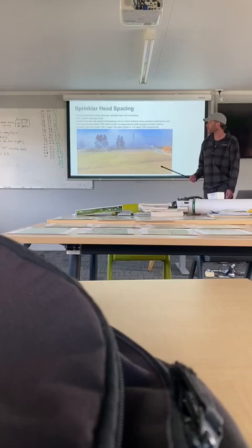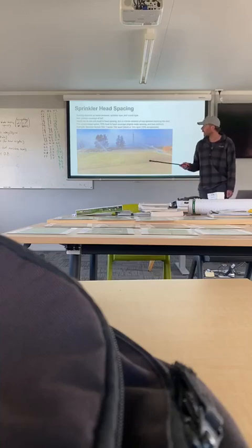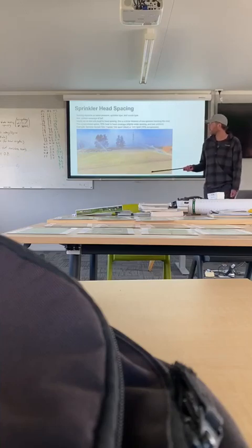We could compromise this by having a rule of 70% head coverage, which will give us slightly wider spacing and less uniform coverage. An example: if we've got a 10 metre throw, ideally we want 10 metres apart, or 14 metres apart would be within the 70% rule.